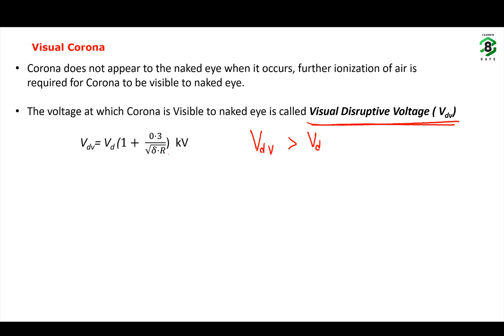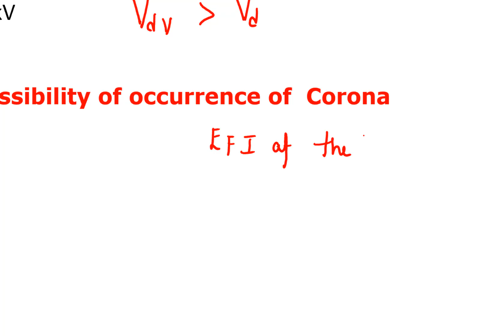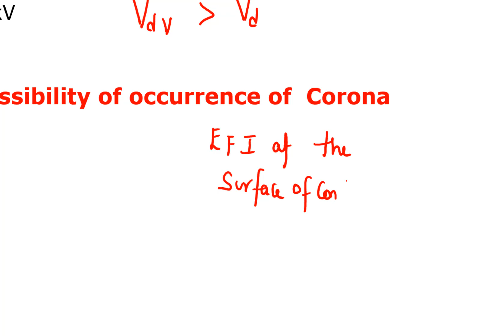So, methods to reduce the possibility of occurrence of corona. How can we reduce the corona? See, again I am reiterating the fact, the electric field intensity at the surface of conductor is given by phase to neutral voltage of the conductor divided by r, the radius of the conductor, into logarithm of D by r, where capital D is the spacing between conductors and r is the radius.